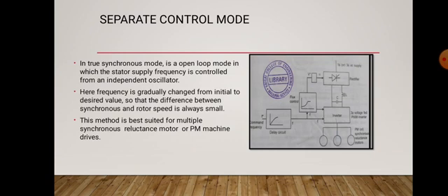What is the separate control mode? See in this figure we have an inverter, where a number of synchronous motors are connected in parallel and connected to the inverter. By changing this inverter's frequency, we can change the frequency of the synchronous motor so that the speed can be adjusted. Here there is a command frequency, and that will be given to the inverter after passing it to a delay circuit. This command frequency will vary from the initial to the desired value.